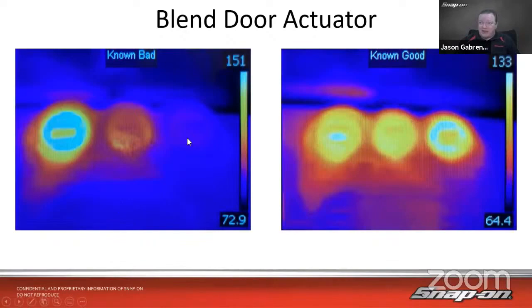So in this case, one of those actuators wasn't working. I got hot air coming out the left vent, no air coming out the right vent. On the right-hand side, we see we got hot air coming out of both vents, that's after it was fixed. So we can see if we have a bad actuator or the door gets stuck, that's happened before too. Thermal camera is definitely a good way to diagnose that for sure. As you can see, we have a definite difference in whether or not that's working.